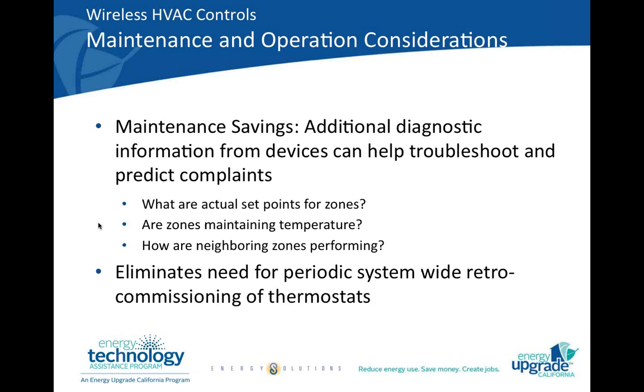As I mentioned before, there can be significant maintenance savings from both of these technologies. Basically, your facility staff are able to get additional diagnostic information from the devices, be able to monitor zone temperature in the case of the WPTs, the branch pressure for your pneumatic system, to identify problems before occupants notice, figure out how the zones are operating and fix them. This eliminates the need for periodic retro-commissioning and allows for real-time retro-commissioning, so to speak. Next slide, please.